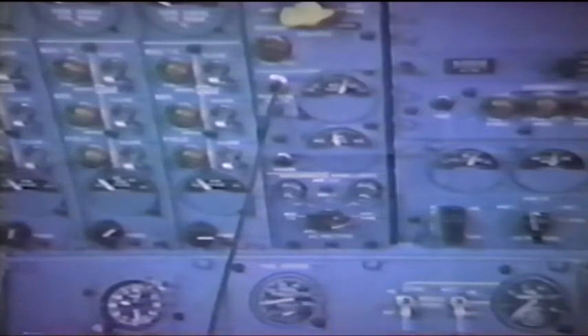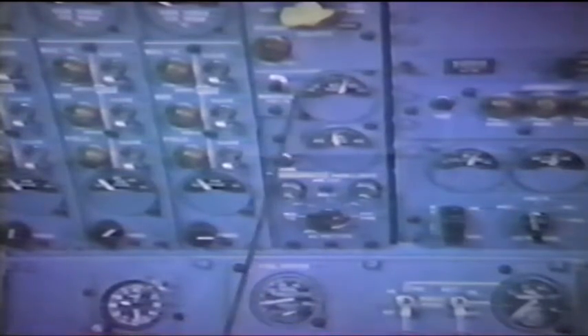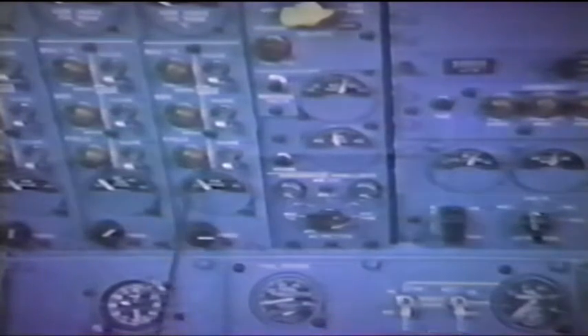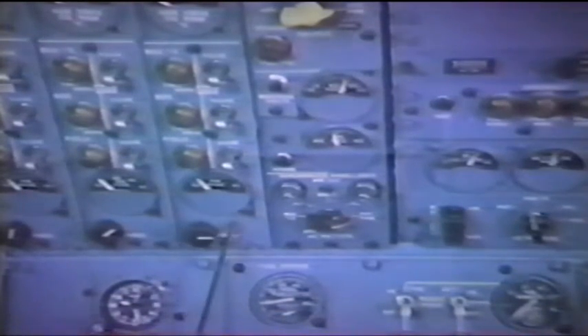Now, when we press the residual volts button, we're changing the AC voltmeter scale from a 130 volt scale to a 30 volt scale. So naturally we would not want to press that unless our selected generator was not putting out 115 volts. And when is that? When we've disconnected it, among other things, when we've opened the field. In cases such as that, when we've turned the generator off and we just want to see what the internal operation of the generator is doing, then we could measure the field current by pressing residual volts. And we should get something like 10 to 15 volts.